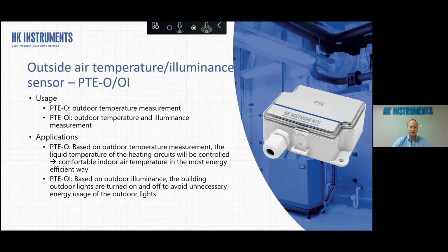And then we have this combination of the outside air temperature and the illuminance sensor, which is totally passive. Especially here in the northern countries, we are using this outdoor illuminance to control the outdoor lights, because the length of the day here is varying a lot. For example, now at this time of the year, I can hardly see any bright sunshine at all throughout the next few months, so no light at all. But in the summertime, it's completely the opposite. There will be bright day and night.